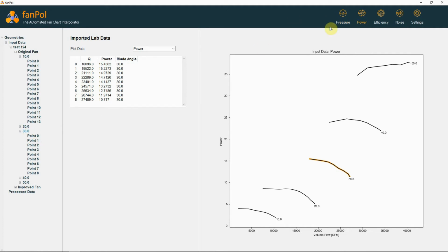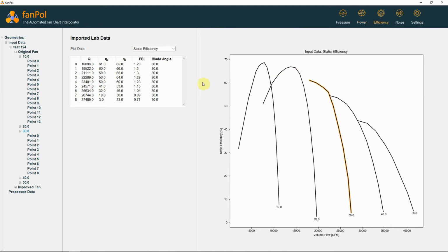If you navigate to Efficiency, you'll see useful information about the fan efficiency. There, you also find the new fan energy index that instantaneously tells you how energy efficient a fan is compared to a baseline fan defined by AMCA. If you want to know more about the new metric, feel free to check AMCA's website and check for Standard 208.